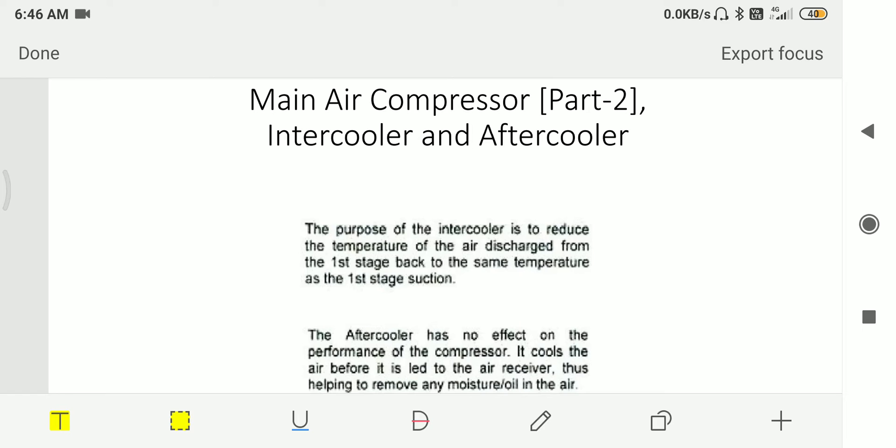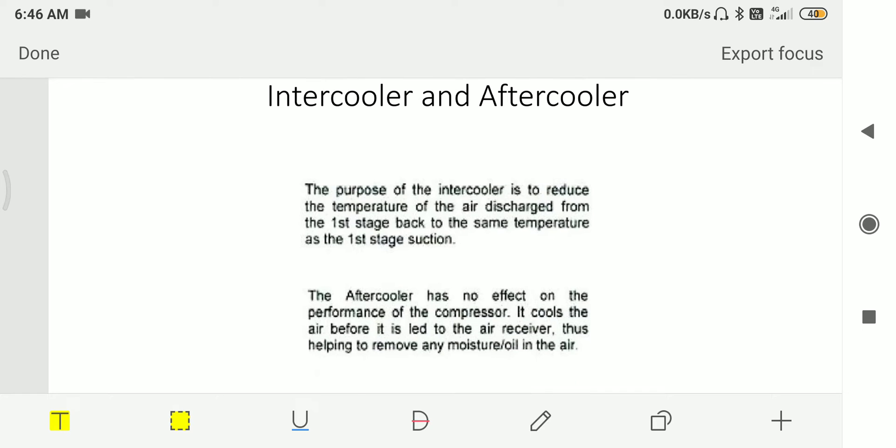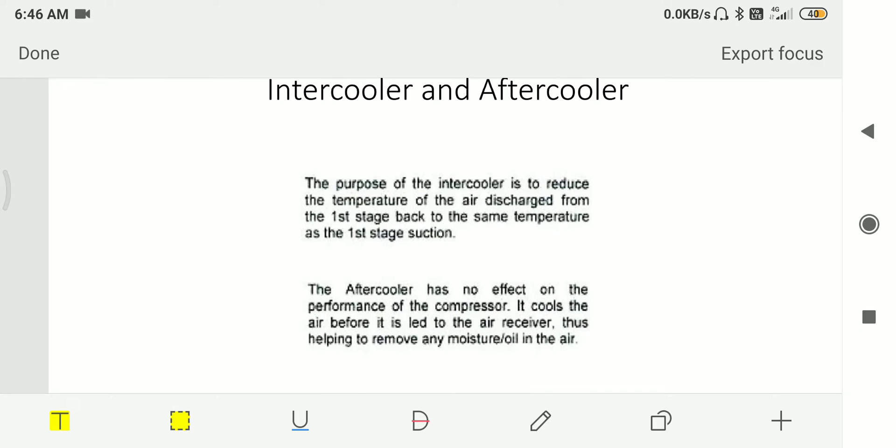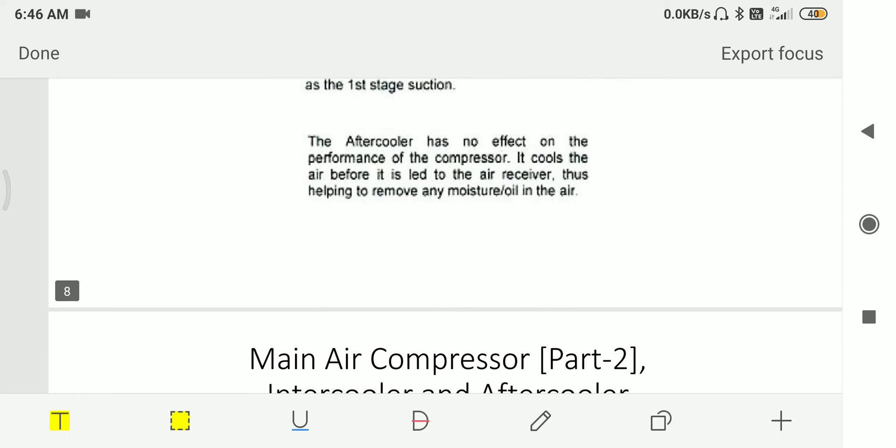Then we have intercooler and aftercooler. The purpose of intercooler is to reduce the temperature of the air discharged from the first stage back to the same temperature as the first stage suction, that is to make the compression process isothermal. Aftercooler has no effect on the performance of the compressor. It cools the air before it leads to the air receiver, thus helping to remove moisture in the air.